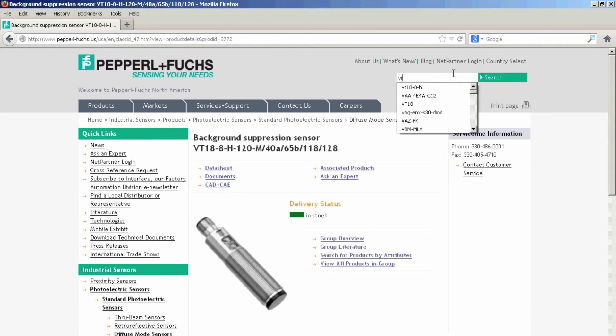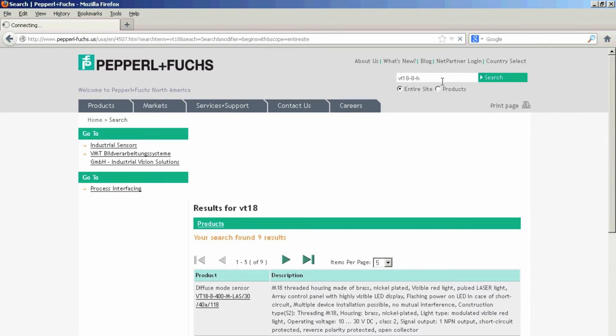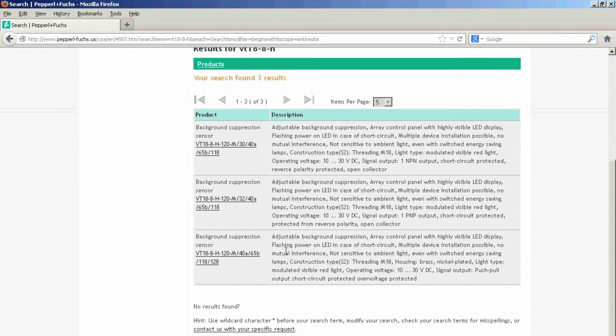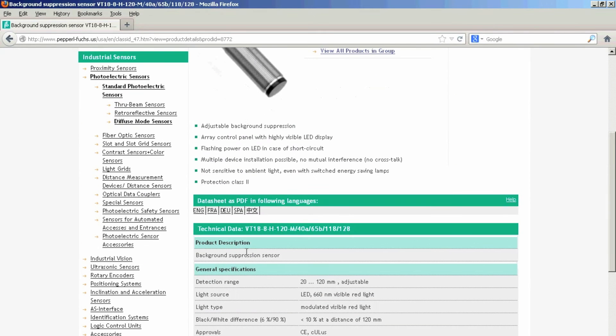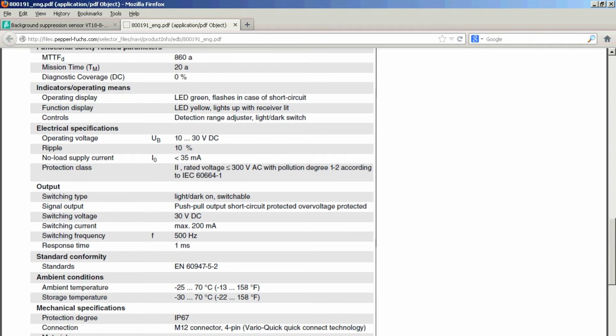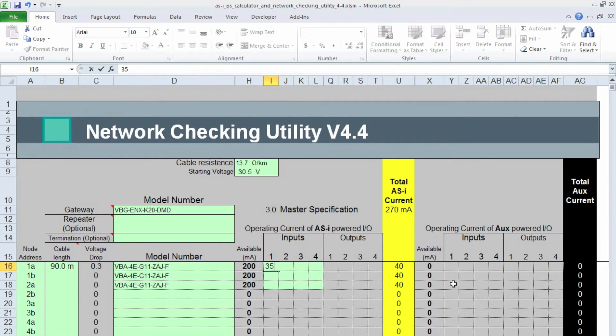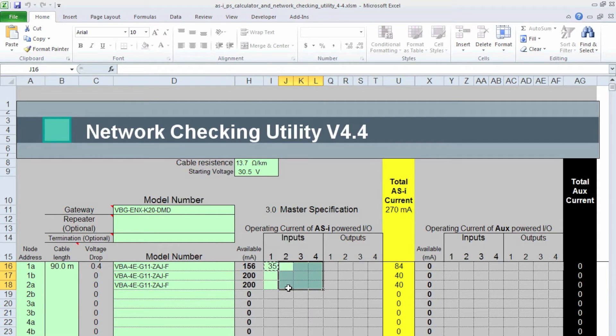And now I'm going to need the operating current of the VT18 sensor that I had connected to all the modules. So what I'll do there is I'll go to the website. Just type VT18. Okay, so it's this VT18-8-H laser here with the background suppression. And if we open the data sheet up, we'll see that in the electrical specifications, the no load supply current is 35 mA. So that's the number I want to put in my sheet. Even though it's conservative, it's still the right number to use. So 35 here.